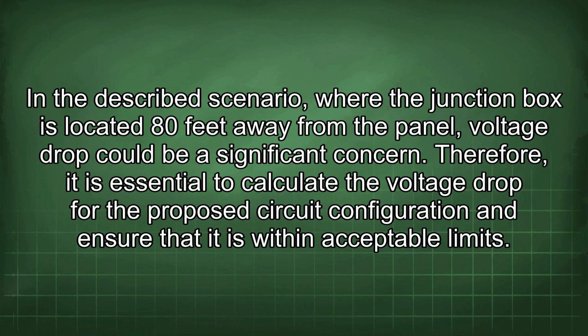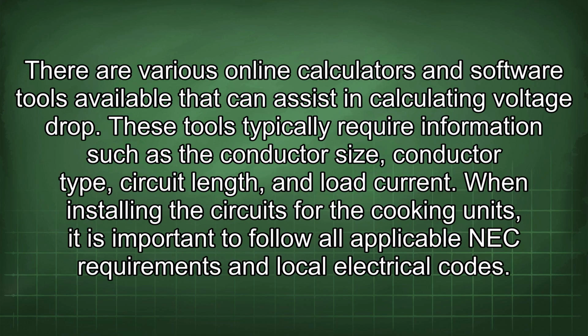In the described scenario, where the junction box is located 80 feet away from the panel, voltage drop could be a significant concern. Therefore, it is essential to calculate the voltage drop for the proposed circuit configuration and ensure that it is within acceptable limits. There are various online calculators and software tools available that can assist in calculating voltage drop. These tools typically require information such as the conductor size, conductor type, circuit length, and load current.